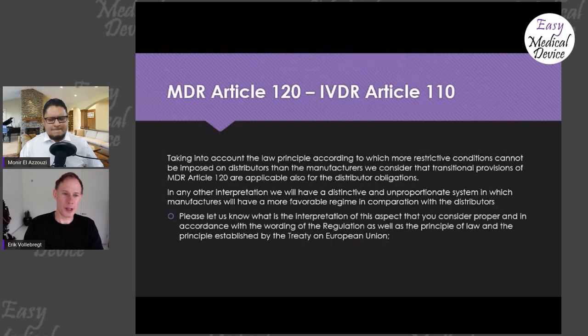There are two aspects to this. There's the MDR itself that says every economic operator has their own responsibilities. And then there's the ISO 13485 standard that says you need to control your supply chain to a certain extent. Exactly. On the second part, the ISO obligations, nothing changes. Whereas on the MDR, each economic operator has their own responsibilities, and the MDR does not impose a direct obligation on you to control them. Actually the MDR does rather the opposite. It says, distributor, if you see this, then you must do that. Importer, if you see this, you must do that. It doesn't say the manufacturer must ensure that the importer does this or that. That's completely not how the MDR is set up.